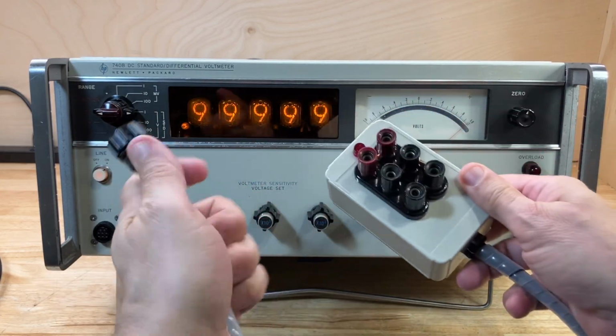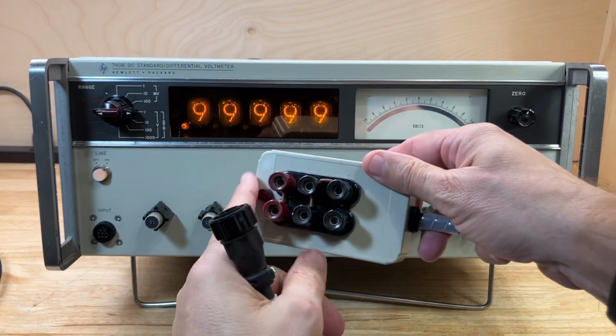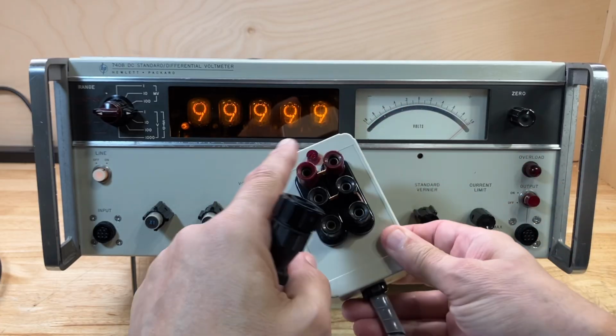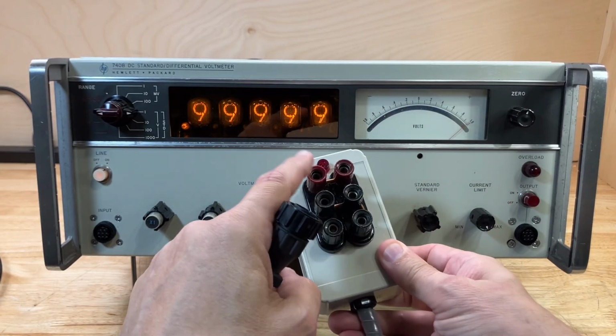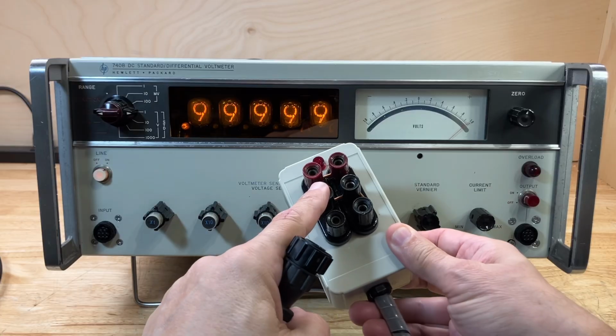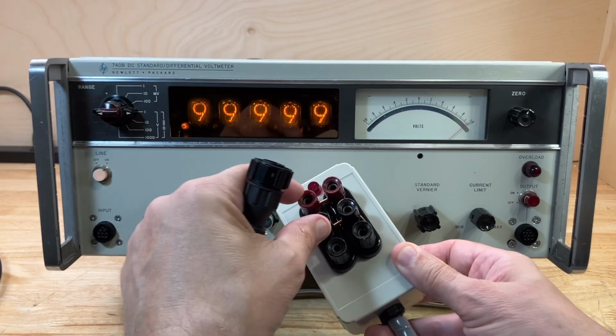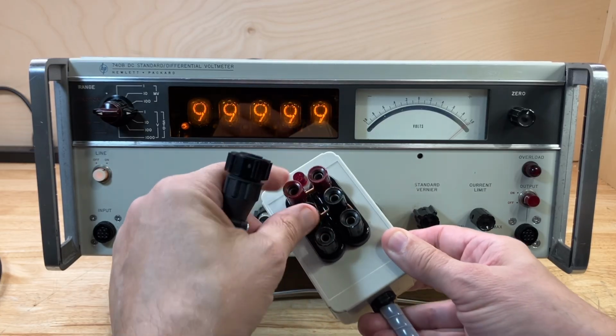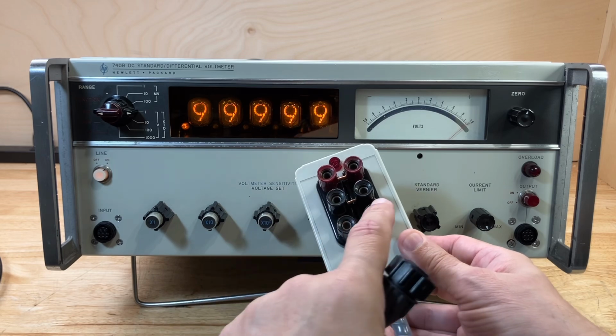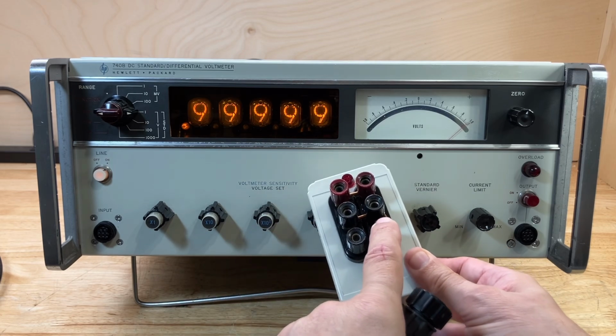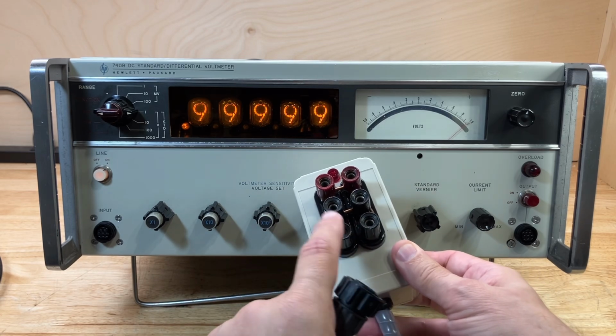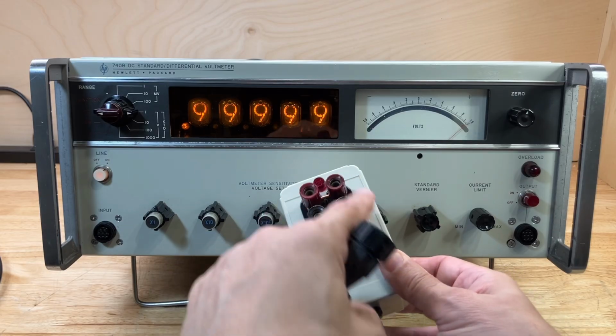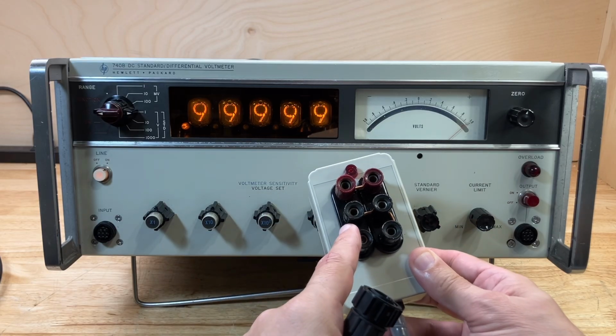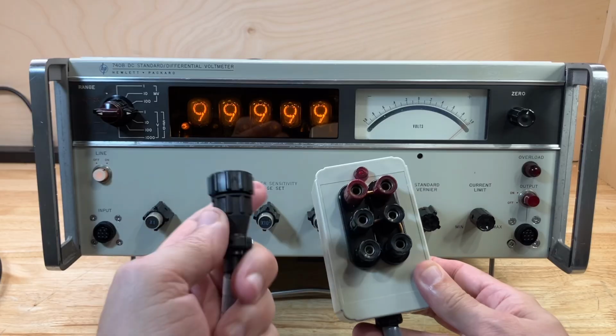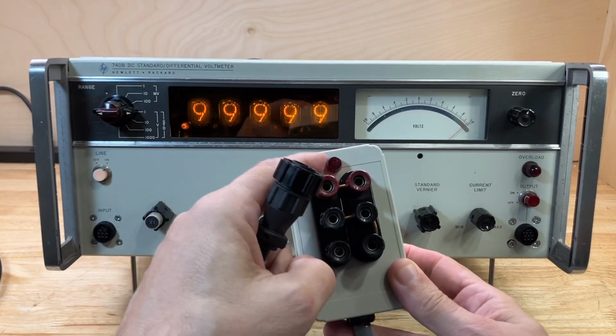Here is the output cable box assembly, here's the connector, and here are the output terminals: a high and low output terminal, a high and low remote sense terminal for 4-wire type sensing, plus a guard terminal and an earth chassis ground terminal. So there are 6 terminals on the output cable, and a connector on the other end of the cable.